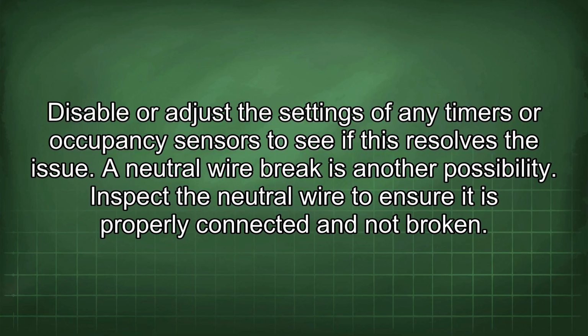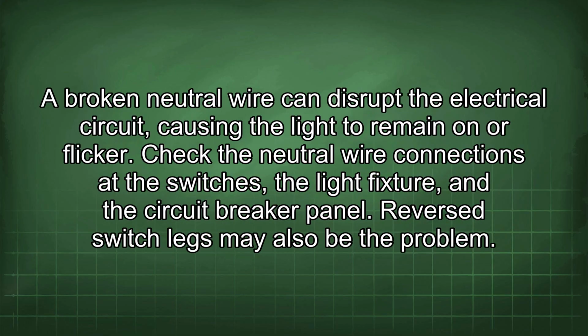Inspect the neutral wire to ensure it is properly connected and not broken. A broken neutral wire can disrupt the electrical circuit, causing the light to remain on or flicker. Check the neutral wire connections at the switches, the light fixture, and the circuit breaker panel.